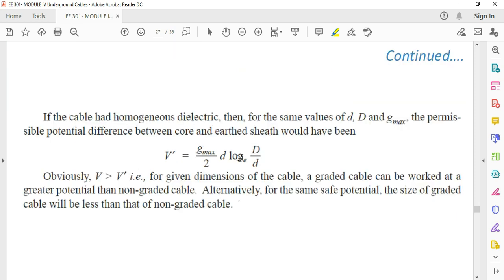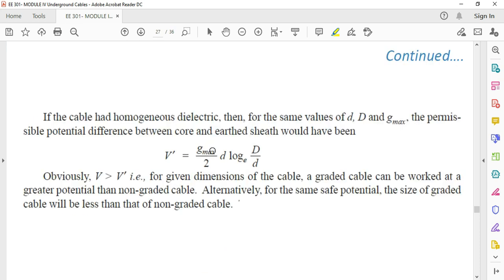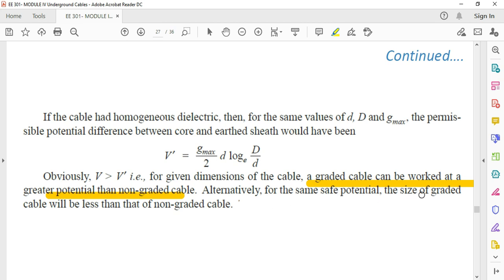In a cable with homogeneous dielectric, the equation becomes gmax/2·d·log(D/d). We can say that V is always greater than V'. So in a graded cable, it can work at a higher potential than a non-graded cable. Alternatively, for the same safe potential, the size of the graded cable will be less than the non-graded cable. That is the advantage of graded cable.